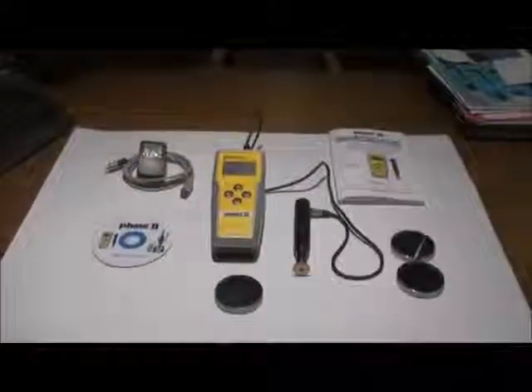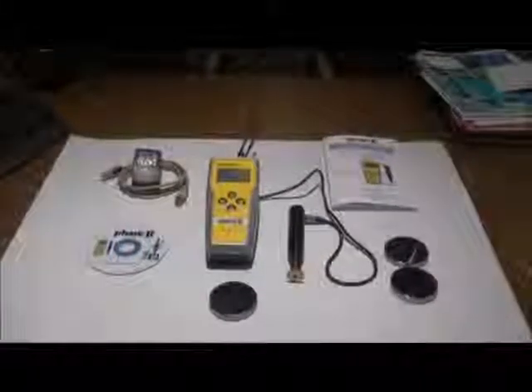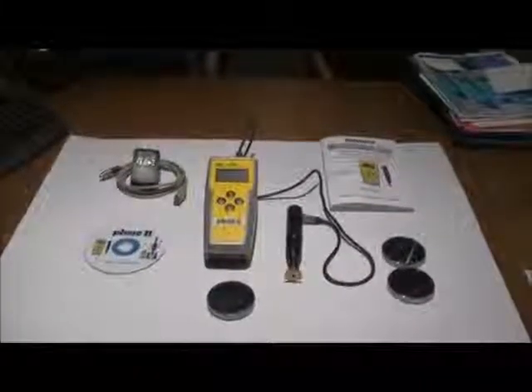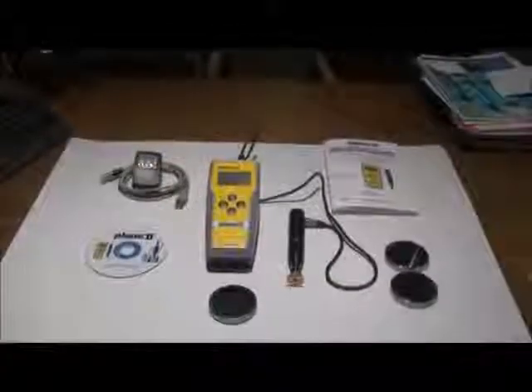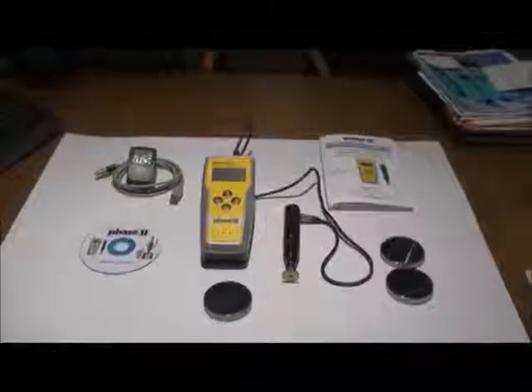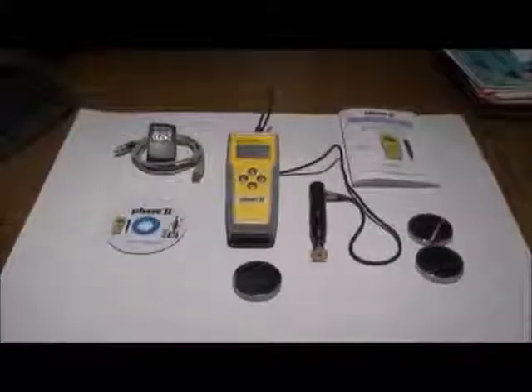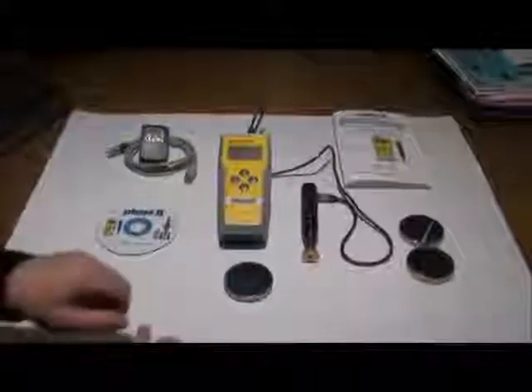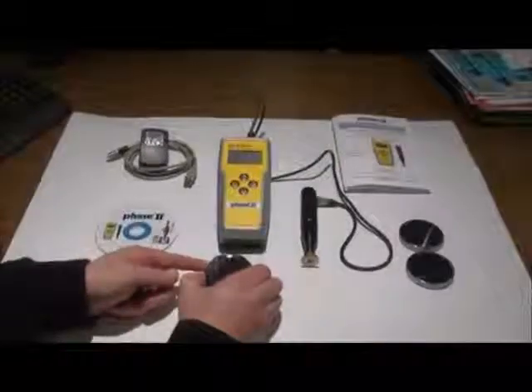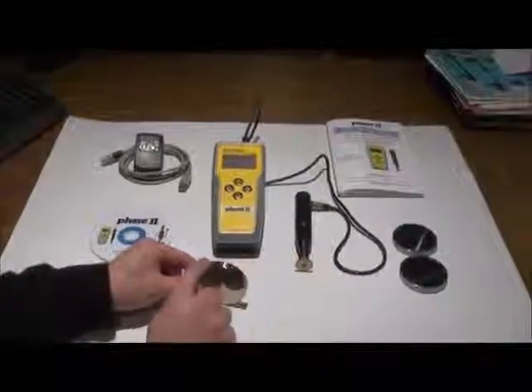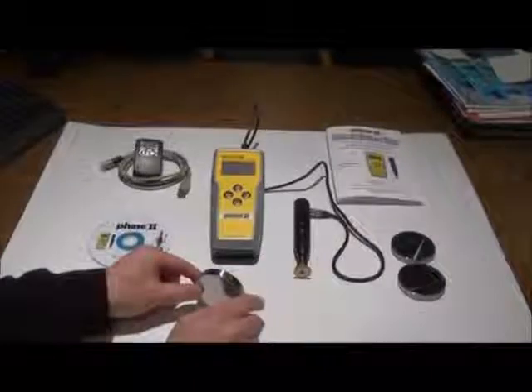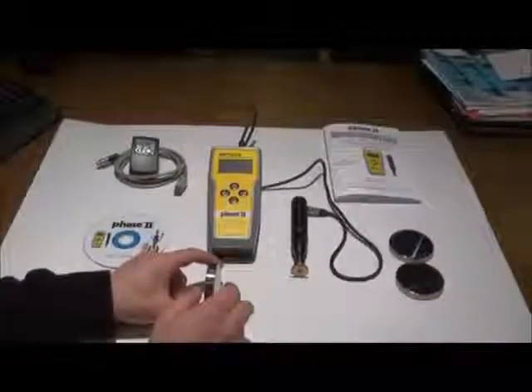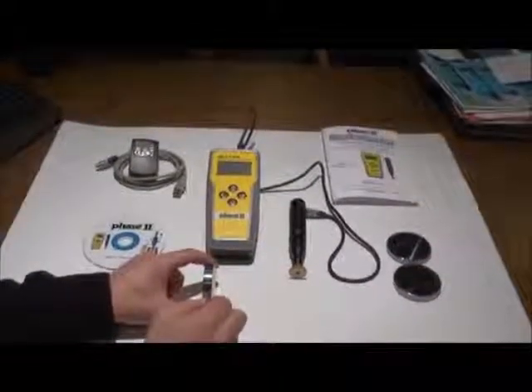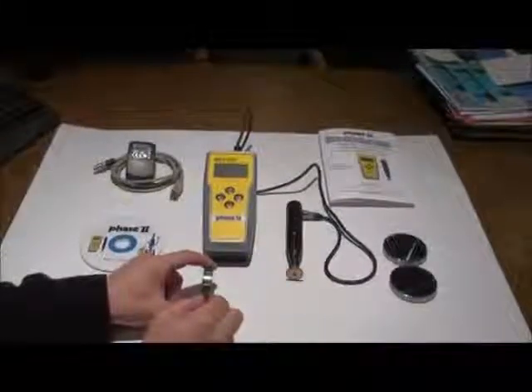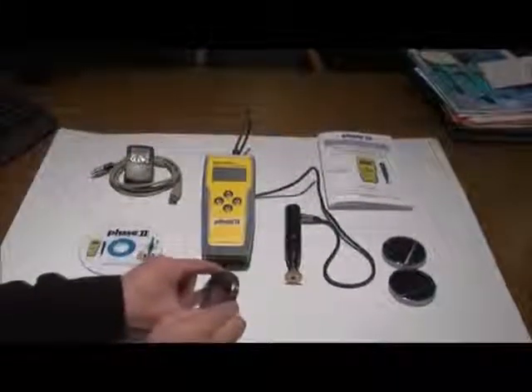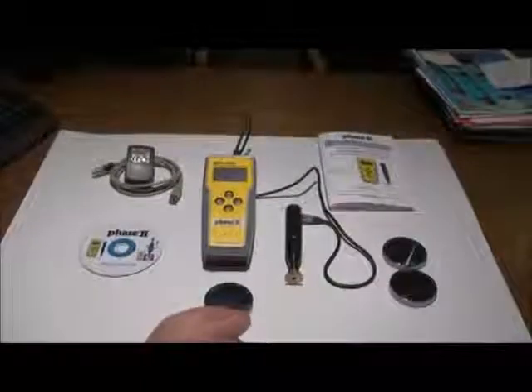UCI, or ultrasonic contact impedance, is the measurement of the frequency shift of a resonating rod tipped with a Vickers diamond after applying a fixed force against the surface of the part to be tested. Certain workpiece parameters must be met for the UCI system to work properly. The minimum radius for a test is 5 mm. The workpiece needs a minimum thickness of approximately 1 mm. However, in the field, without support, that number may vary up to 2 mm, depending on the material being tested.